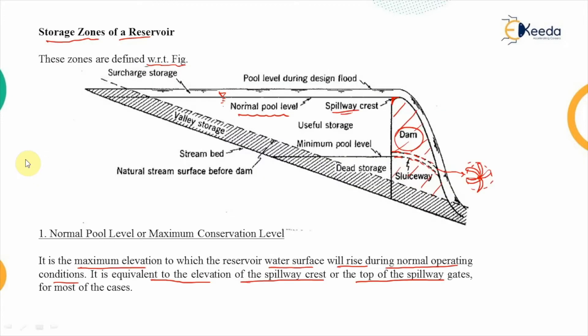The minimum pool level is also guided by the minimum head required for efficient functioning of the turbines. If the sluiceway is at the lowest outlet position, we must maintain the minimum pool level corresponding to that sluiceway, and that will dictate the head governing the functioning of the turbine placed across it.